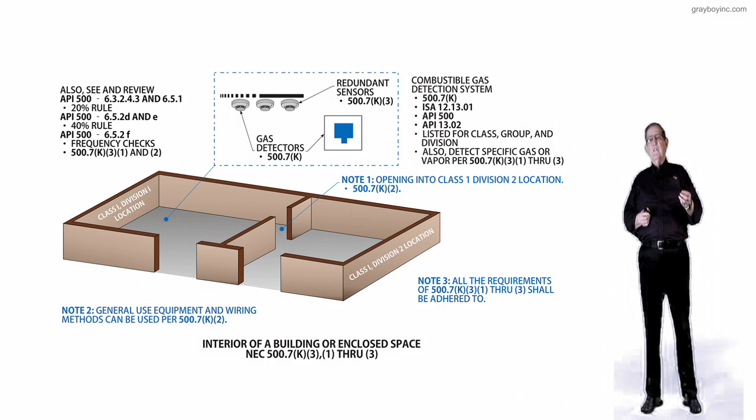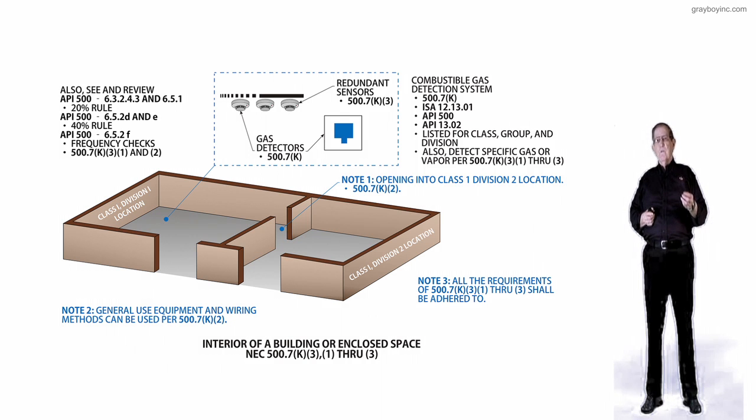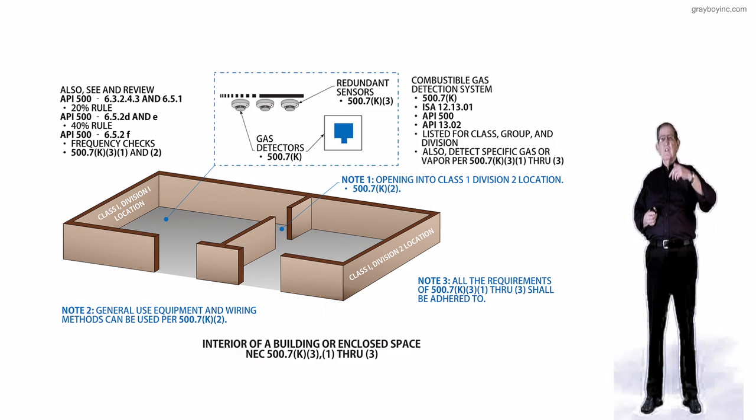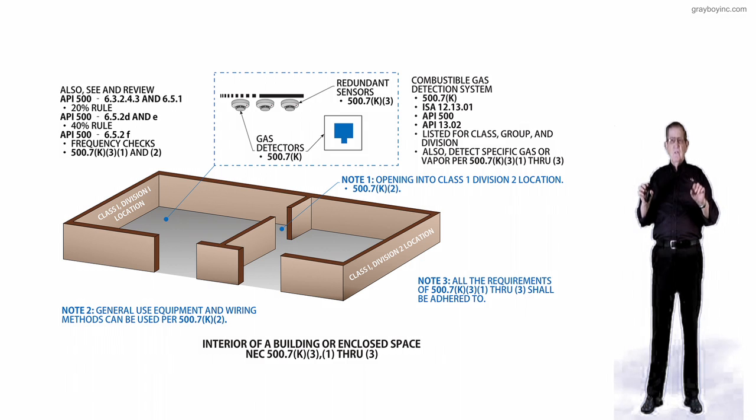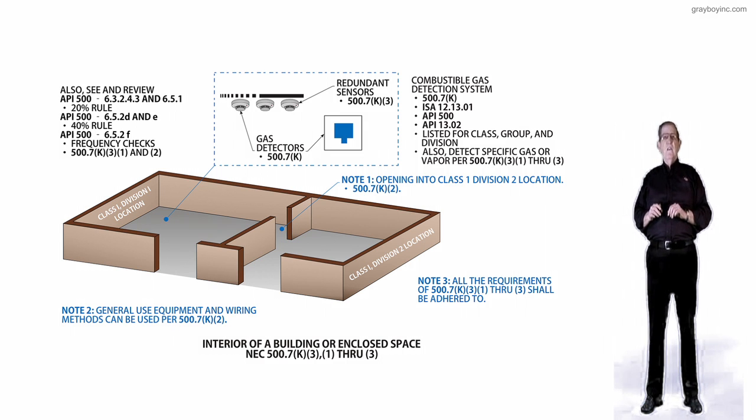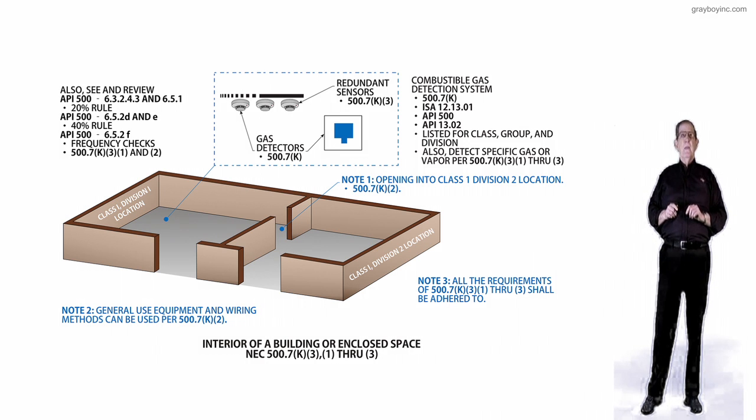But on its way from the lower flammable limit up to the upper flammable limit, that's where it's very dangerous and in a very explosive range. Once it gets above the upper explosive limit, then we know that it's too rich. So usually that's how the engineers will determine how they're going to treat a vapor and what all they have to do to protect from arc, sparks, heat, and that kind of thing.